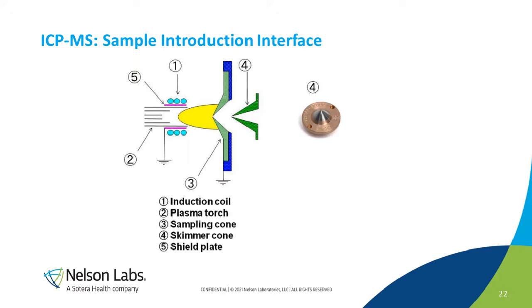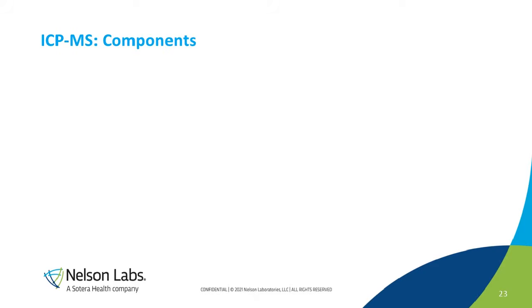This is already showing the actual selection process of the target element, and when it is introduced, carrier gas, argon gas, delivers here the plasma, and then the induction coil and the plasma torch, and then the sampling cone, skimmer cone, and then the shield plate. And this is also showing how our target element could be selected and then introduced into the mass analyzer. I'm showing this one because when we heavily use it, it is going to be dirty, and then probably blacked out, and then later on probably you cannot detect anything. So meaning this one is going to be very dirty, you need to clean it.